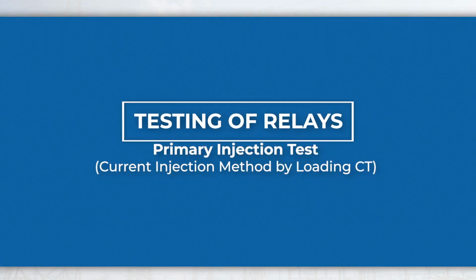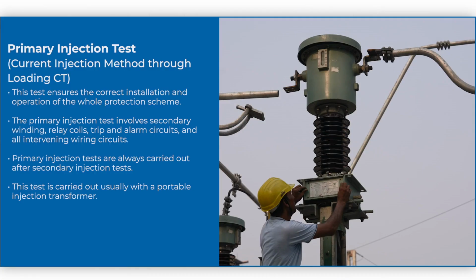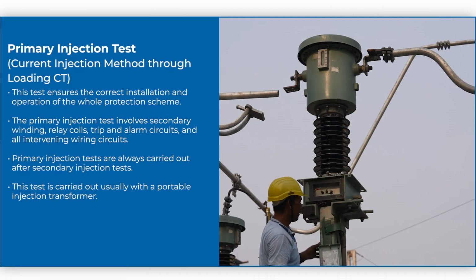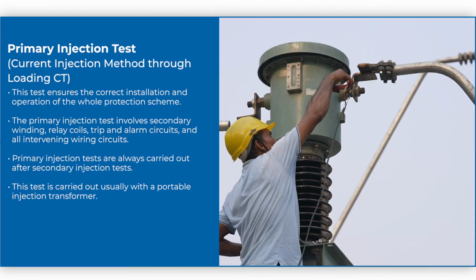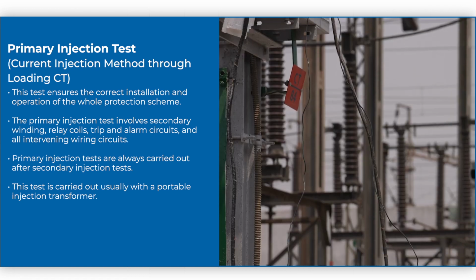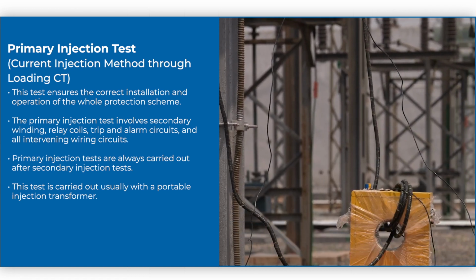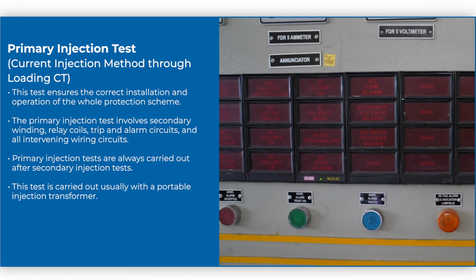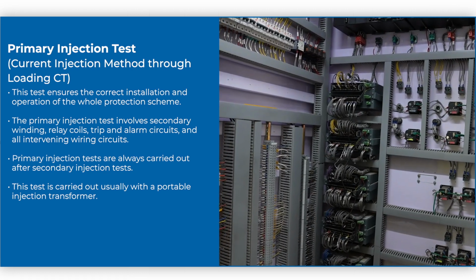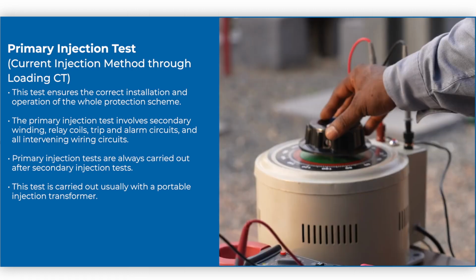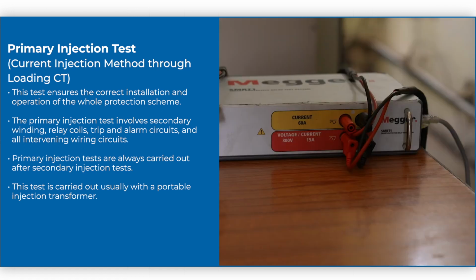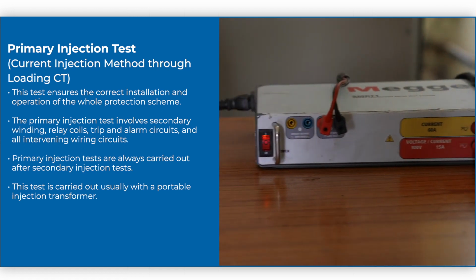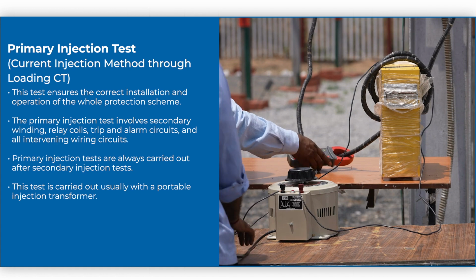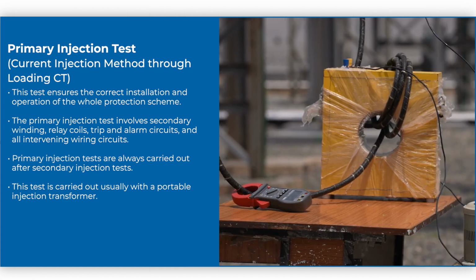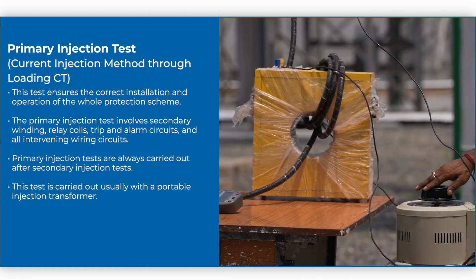Primary injection test, current injection method by loading CT. This test ensures the correct installation and operation of the whole protection scheme. The primary injection test involves secondary winding, relay coils, trip and alarm circuits, and all intervening wiring circuits. Primary injection tests are always carried out after secondary injection tests. This test is carried out usually with a portable injection transformer.